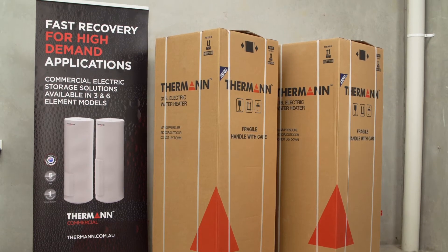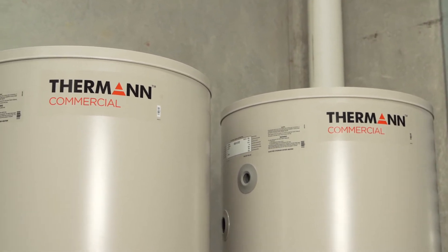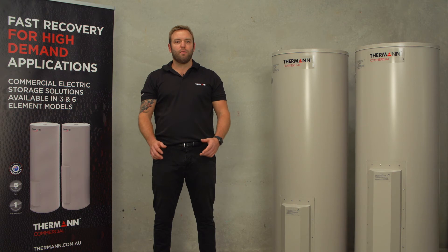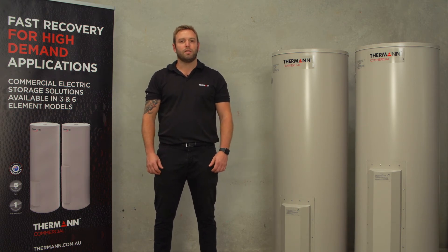Thermann commercial electric storage systems have been designed to be used in commercial applications with large hot water demand and the need for fast recovery. They can be manifolded together for even more heating capacity. With a maximum thermostat setting of up to 80 degrees, they're perfect for jobs which rely on hot water for sanitizing. They require three-phase power to meet the energy draw of running multiple elements at the same time.